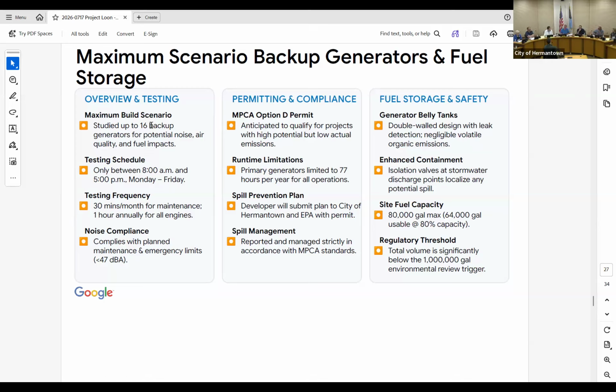One question regarding noise from the backup generators. I noticed the note about noise compliance for planned maintenance and emergency limits. In the event of a power outage, if all backup generators on site had to activate, would that still fall within the noise parameters established for the site? Correct, it does. The loudest noise-generating equipment is what cools the data center itself. If there's a grid outage, since this isn't a fully backed up campus, the cooling equipment gives and takes—it would actually be significantly less noisy if there were a grid outage and only the generators were running.